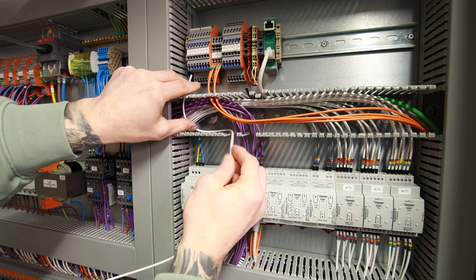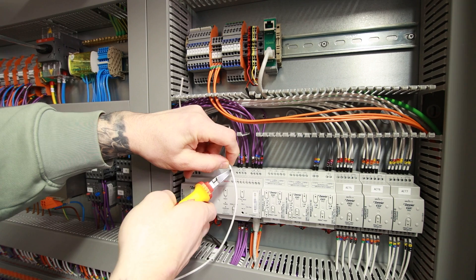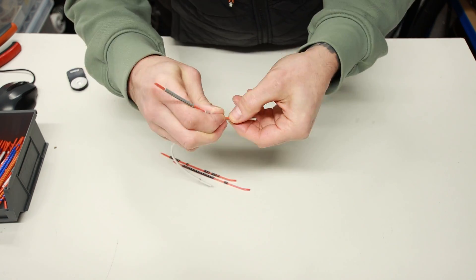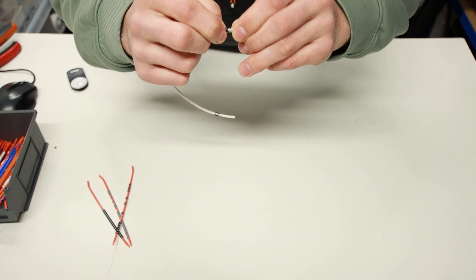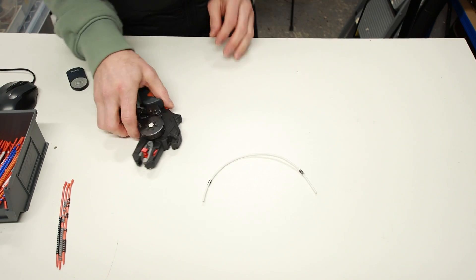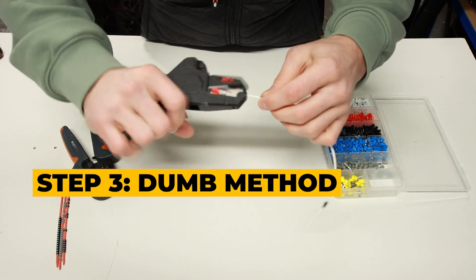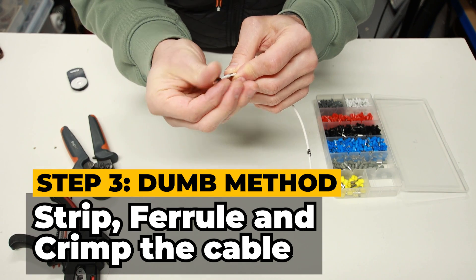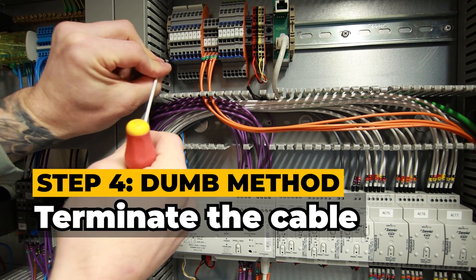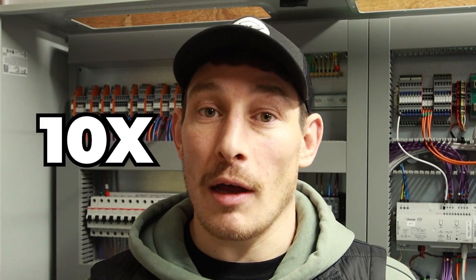The first step is to measure out the cable length. So we start here at the terminal block, get a nice swoop in there, and we're coming to about here. Then we mark that with our finger and thumb and cut it. The next step is to put a cable ident on the cable. Next stage is to strip, get a ferrule on the end, and then crimp them. Move the ident down, and then the final stage is to terminate it. So that's one done. Now I need to repeat this process 10 times.